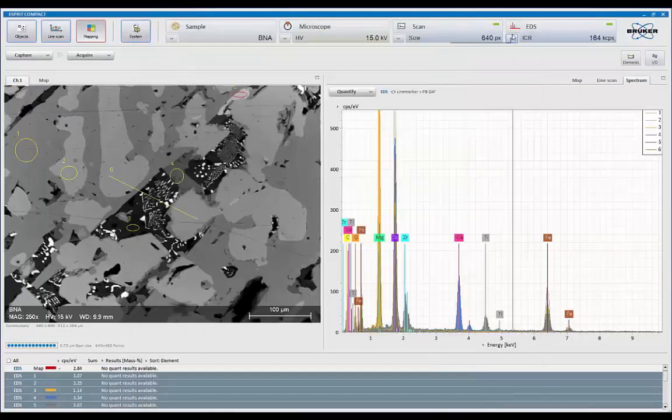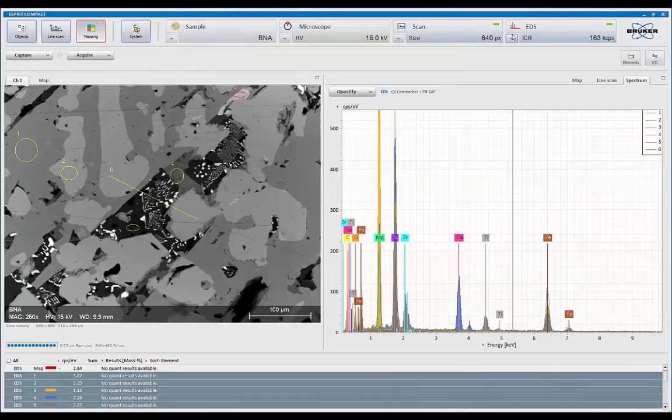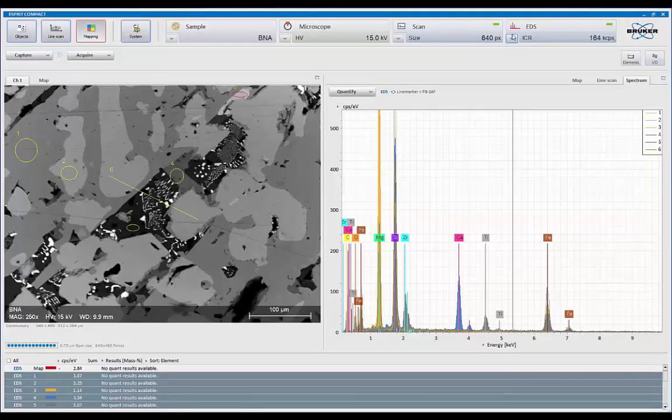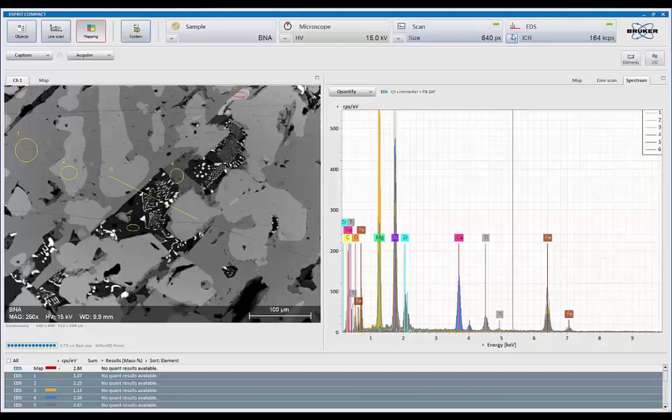And as we keep adding, again, it keeps appending the results. But the key thing with the hypermap collection that this system has, we're collecting all the elements within the spectrum. So if you misidentify an element, forget about an element, discover a new element, you don't have to restart the acquisition. You can just simply go back and tell it, show me this possible element. It gives you the most flexibility that you can have within this type of system.